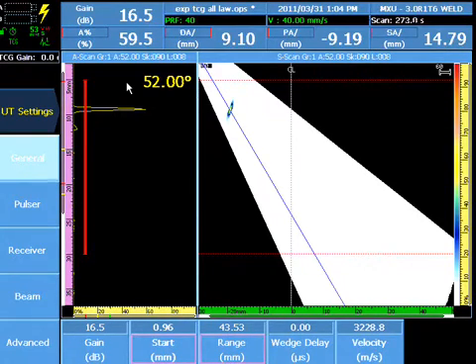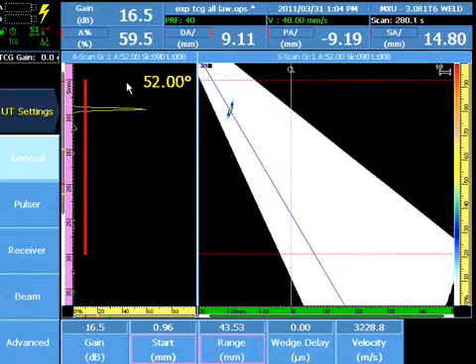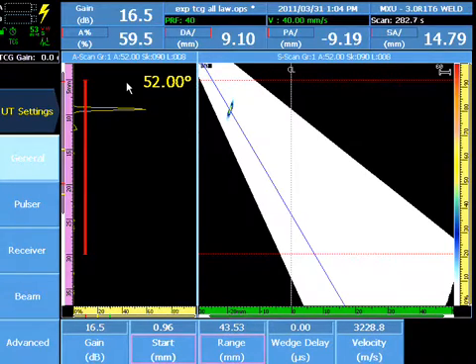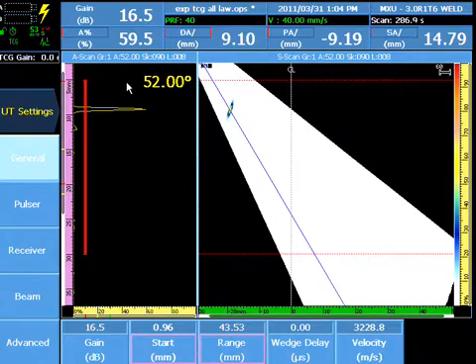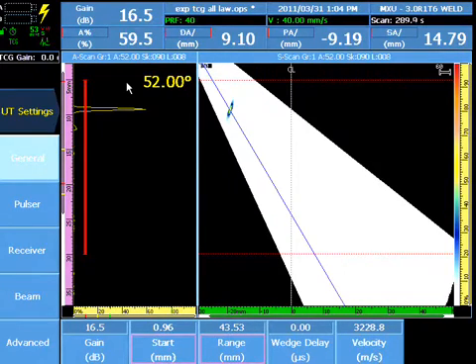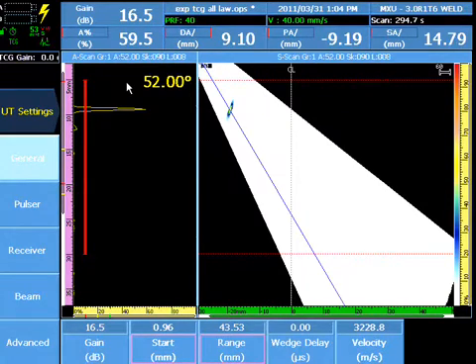The OmniScan MX-2 software contains wizards to make common tasks simple and fast. The TCG Wizard provides a step-by-step guide through the TCG calibration that eliminates the need for repetitive tasks on each focal law. The TCG Wizard uses real experimental readings, not an algorithm, to calibrate each focal law to the same sensitivity on a series of calibration targets at different sound paths.